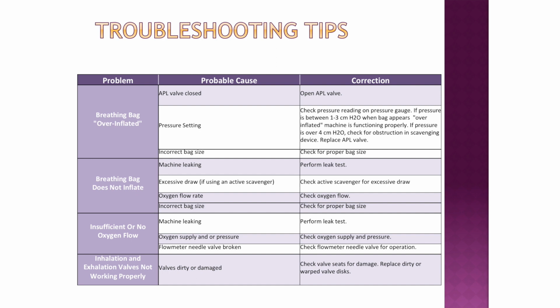Make sure you didn't choose the wrong bag size. If the bag does not inflate, check for leaks. Make sure your active scavenger isn't sucking too hard, because that is conceivable. If it's over adjusted, it's just sucking the gas right out of the circuit. Make sure you've got the right bag size and oxygen flow, make sure you're always plugged into your oxygen system, and double check those inhalation and exhalation valves too.